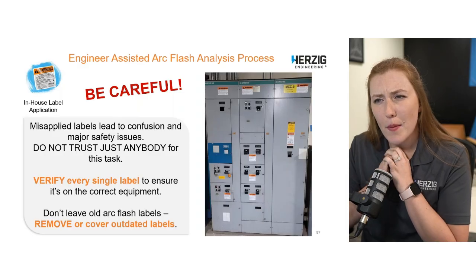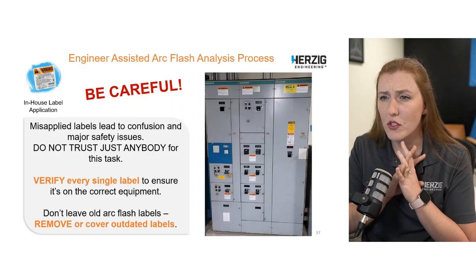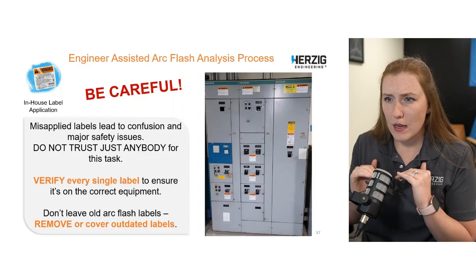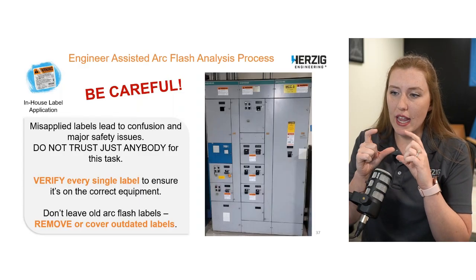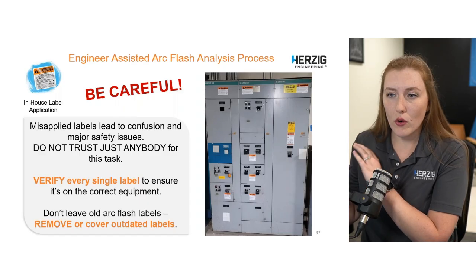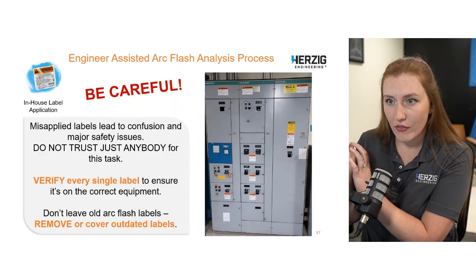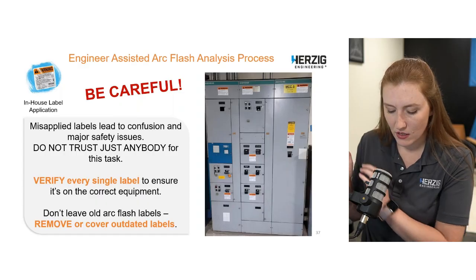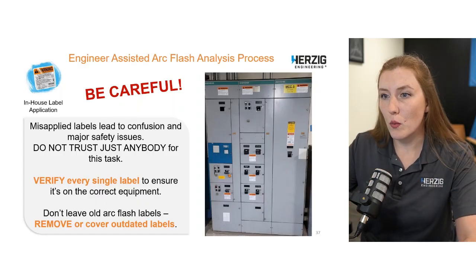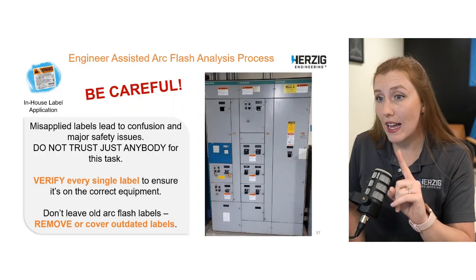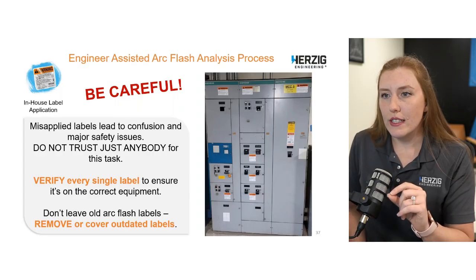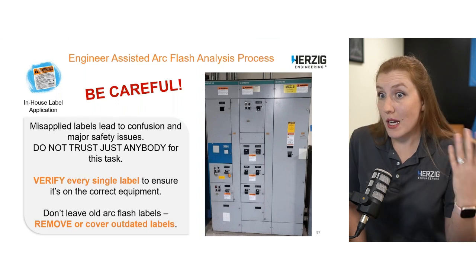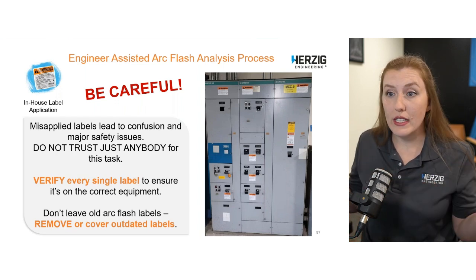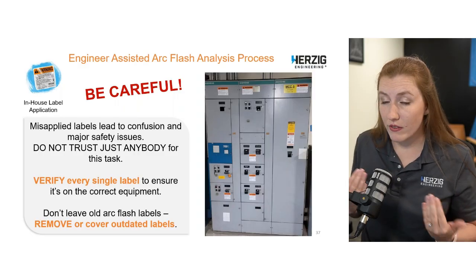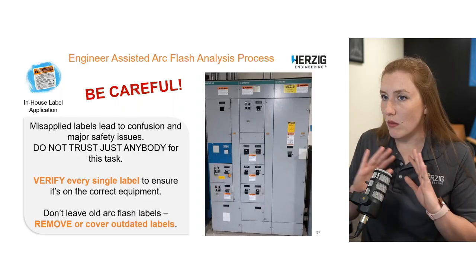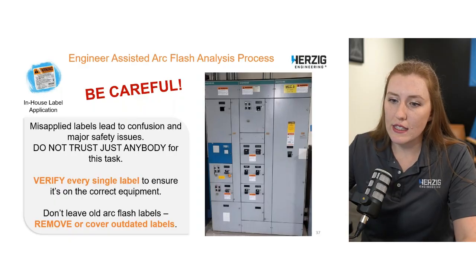It depends on how it's all set up, manual transfer switch or automatic transfer switches, where that label needs to be. So usually it'll have the name and then N for normal, or a second copy with E for emergency, or however that terminology makes sense for you guys. And that would be part of the training as well. But they usually go side by side unless you've decided to do just the worst case. Sometimes it's the normal, sometimes it's the emergency, and then we only send you the one that is the most conservative to, again, avoid any confusion. So that's an option to discuss as needed.